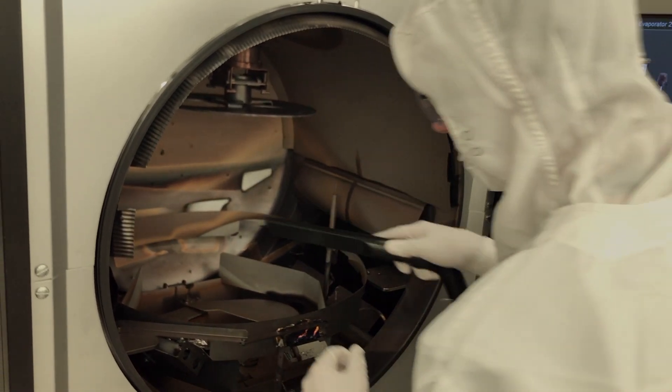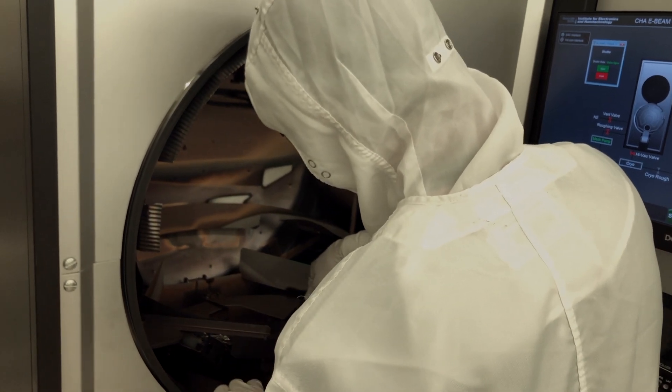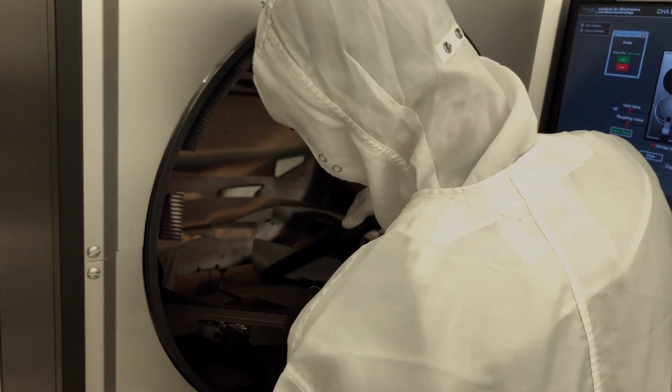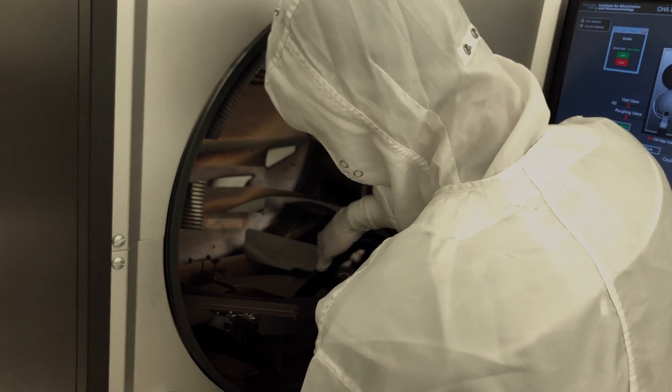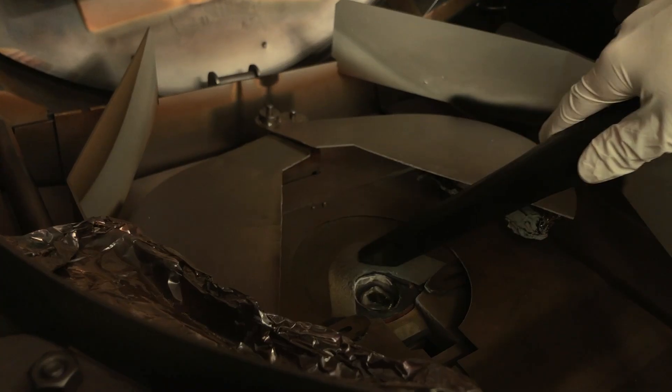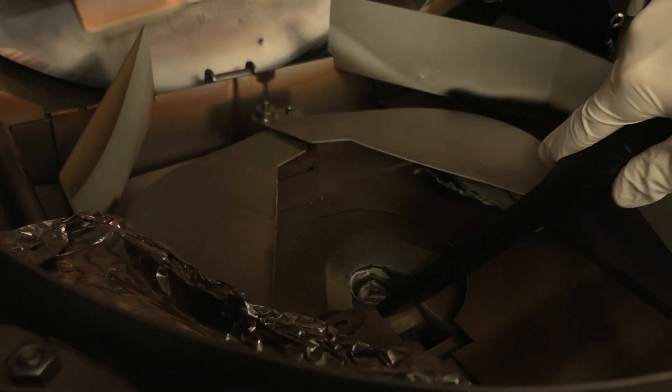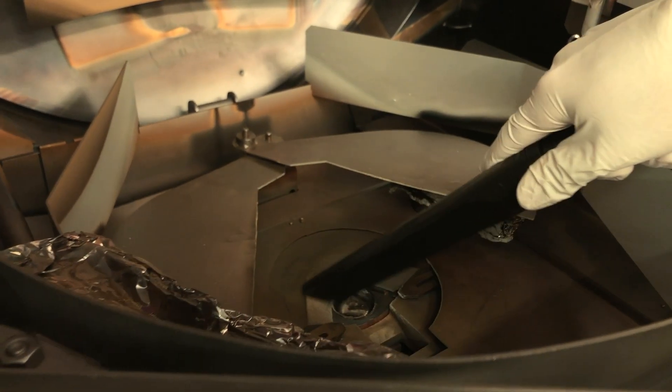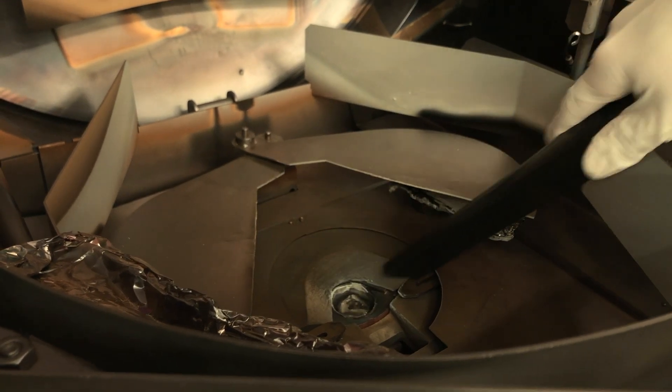You should now take the time to vacuum in and around the chamber. It is important to clean up any debris prior to a process run. A clean chamber will ultimately result in a smoother process run and better results. Vacuuming around the threshold of the chamber will also help the chamber door to form a better seal when the system is pumping down.